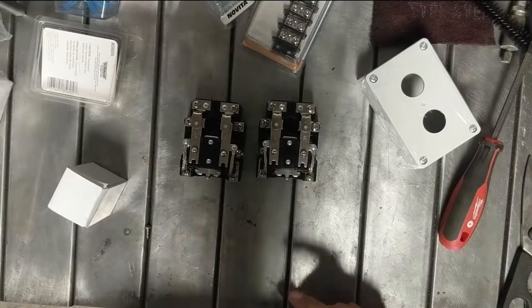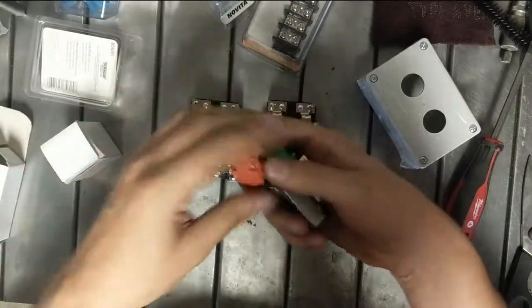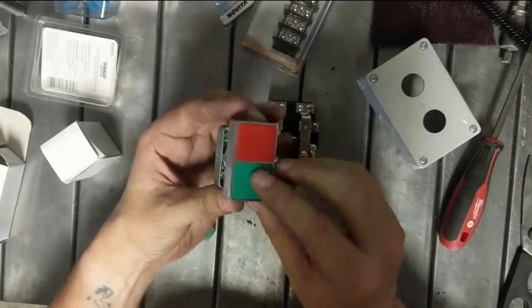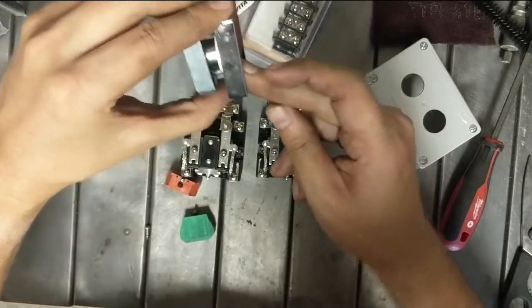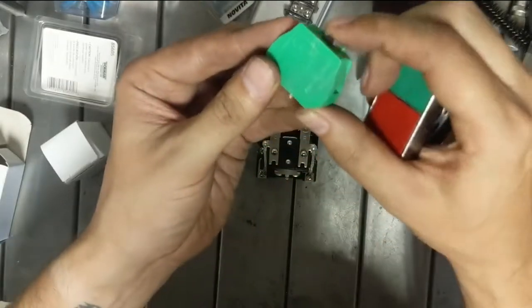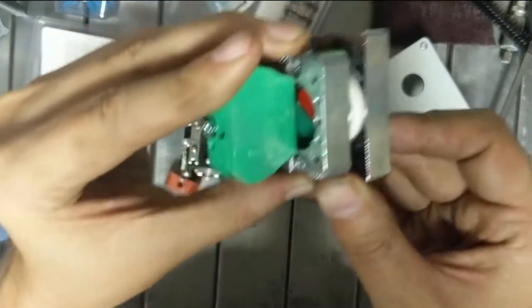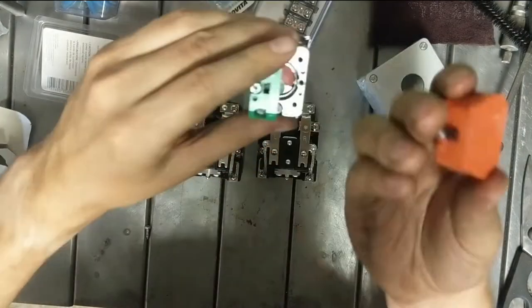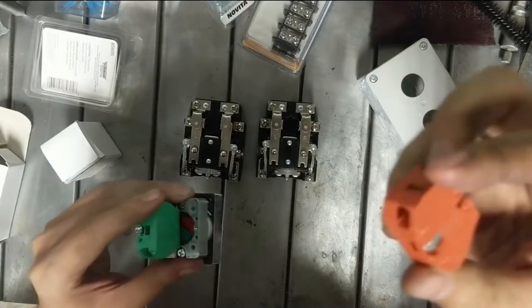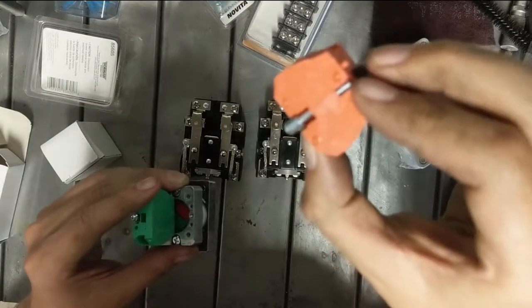What we need to do now is make our control circuits. For that we've got some mechanical contactor switches here. These are momentary switches, which means there's a spring return. This contactor has a cam on it. When I press the green button it makes up that contact. Likewise on the red one, it's got the same cam but this is what's called a normally closed switch, so when this cam gets pressed, this breaks contact.